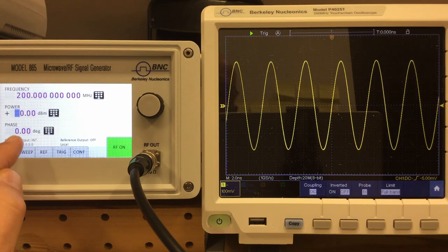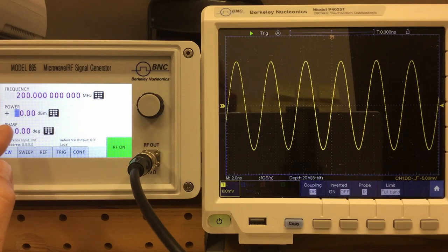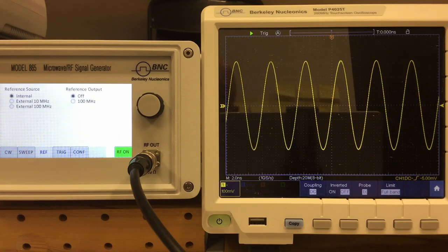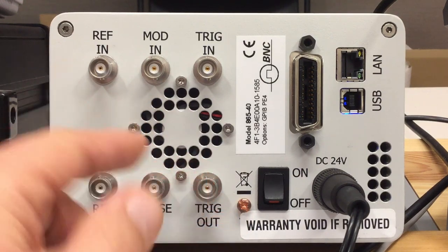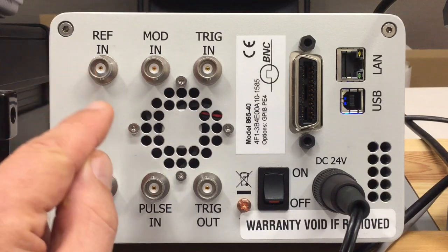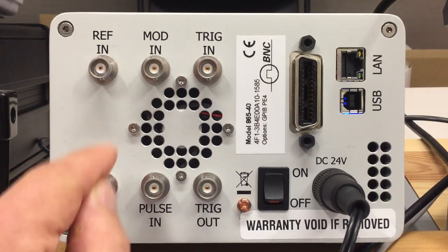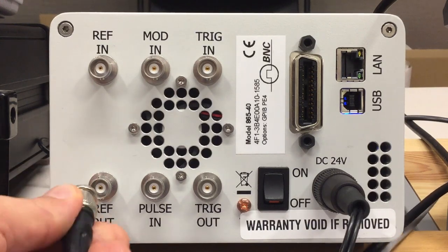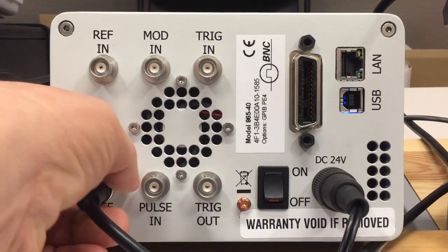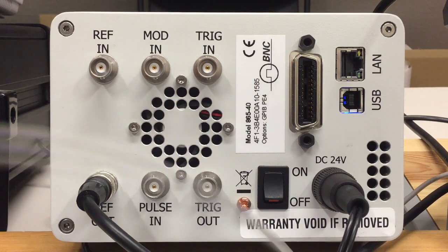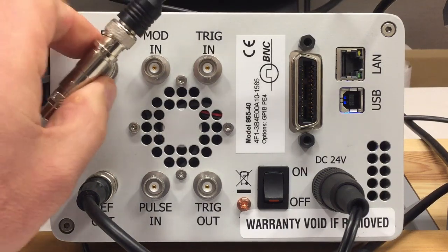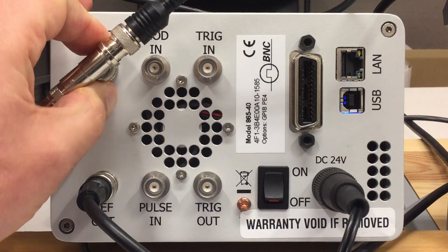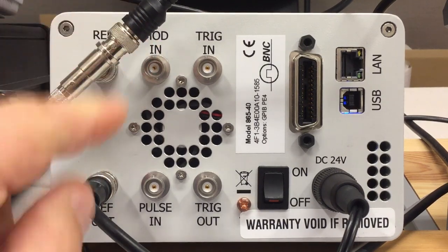Associated with the reference menu, you find two BNCs at the back: reference in and reference out. When talking about reference, we are talking about the 100 MHz oven controlled crystal oscillator in that thing. So let's connect the scope to the reference out, and we'll at least try to feed in an external reference through the reference in, but that might not work out. More about that in a second.